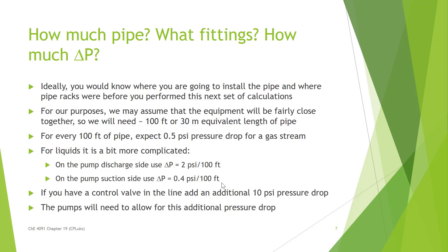If you have a gas stream, you can expect about half a psi of pressure drop over that 100 feet of pipe. For liquids it's a bit more complicated: on the suction side you have about 0.4 psi per 100 feet of pipe, and on the pump discharge side about 2 pounds per 100 feet. If you have a control valve in the line, add an additional heuristic value of about 10 psi across the control valve. So for the pump discharge pipe with a control valve, that's about 12 psi total — a particularly significant value. You need to make sure the pump you selected can handle that extra 12 psi.